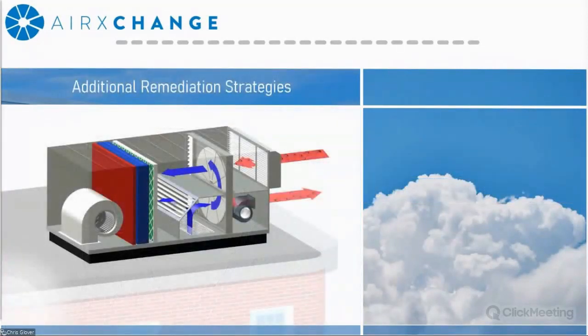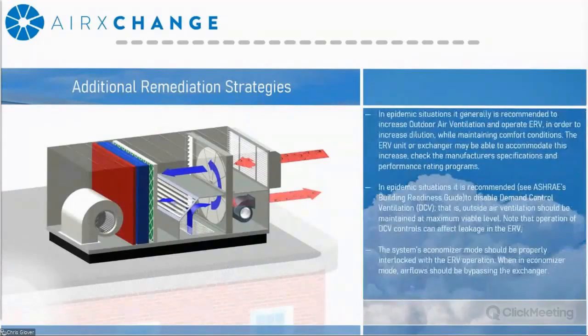And lastly, aside from cleaning, what are some additional remediation strategies? In epidemic situations, it's generally recommended to increase the outside air ventilation to the maximum allowable amount to achieve as much dilution as possible during this time, so long as you're not losing control of the space conditions that would affect occupant comfort. In certain situations, this may be achievable depending upon the design of your system. It's always good to check with a design engineer or with the original equipment manufacturer to determine if this is possible.